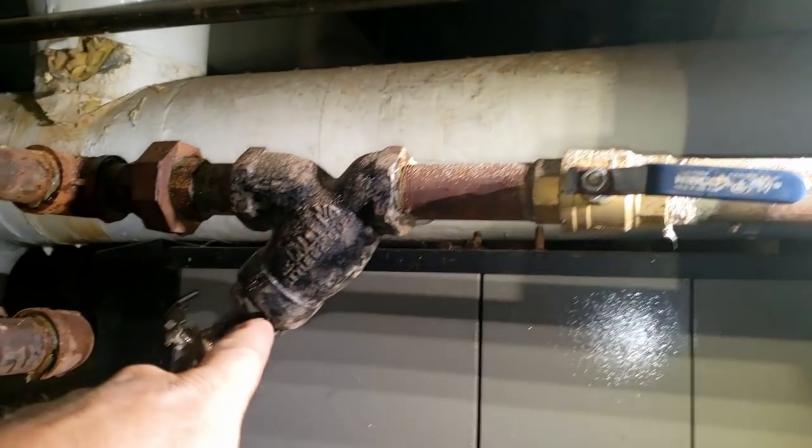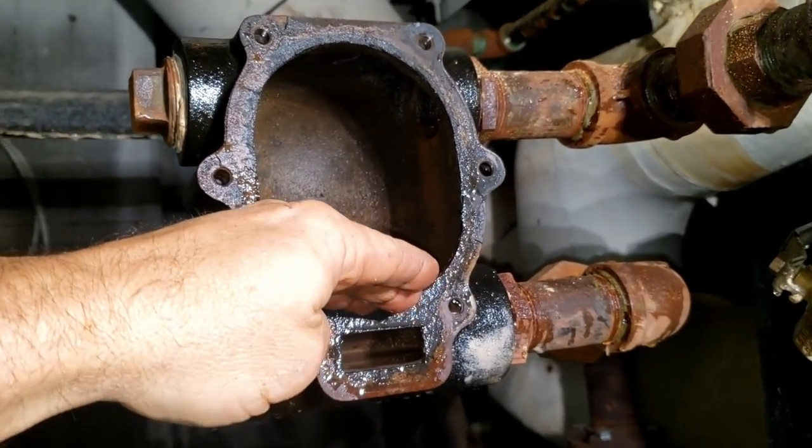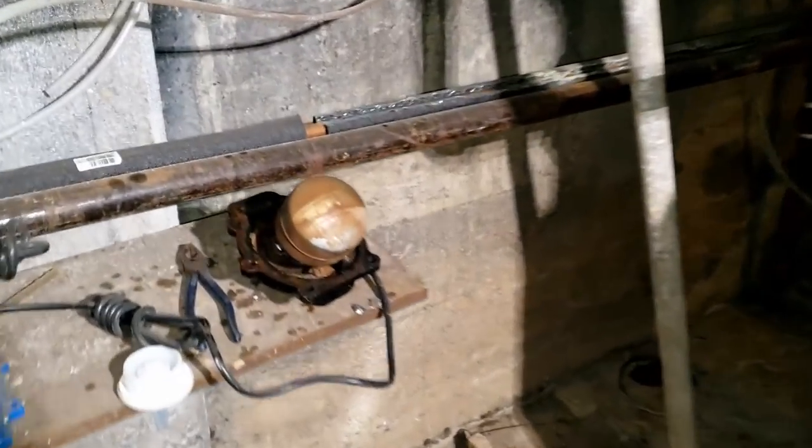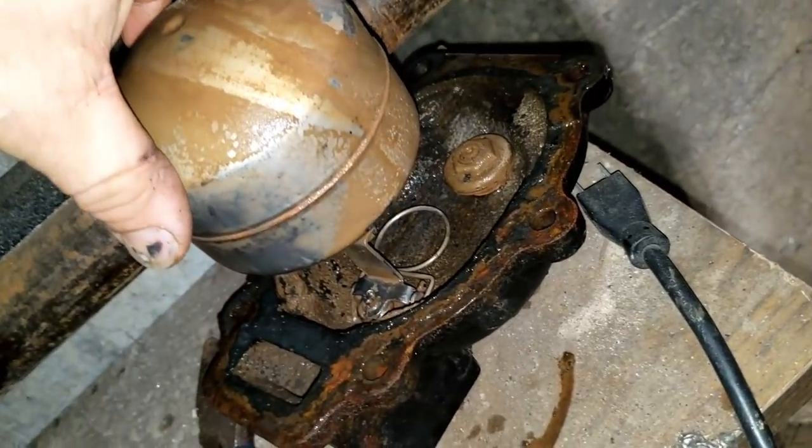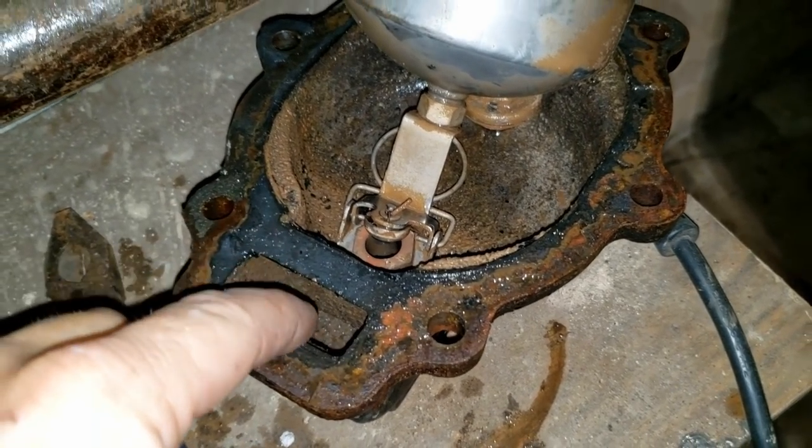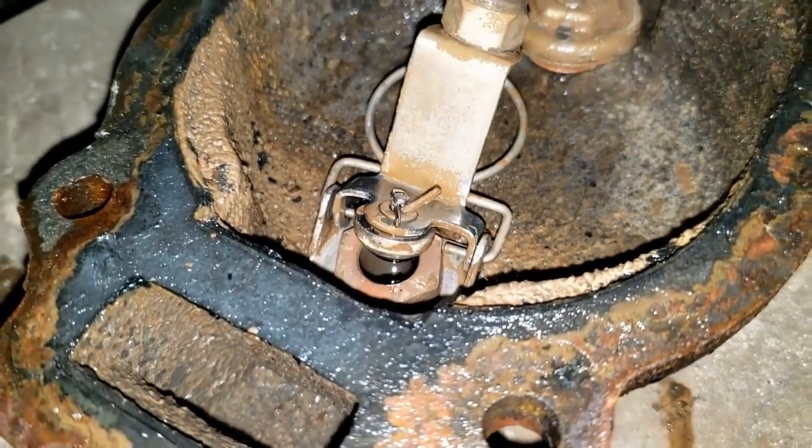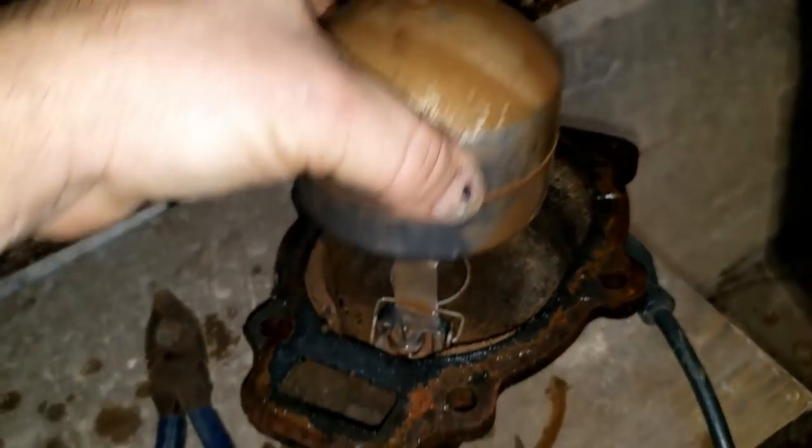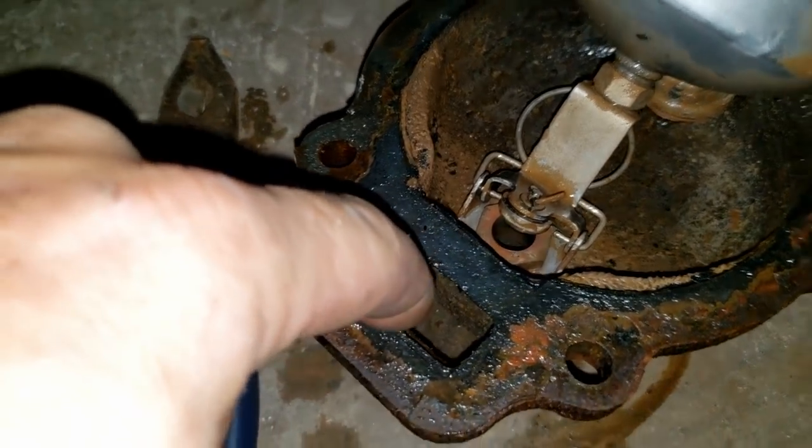This is completely sealed and the water comes in from this top line here on this boiler, goes through, there's got like a blowdown valve so to speak here, comes across, goes into the top. And as it accumulates, it comes up and it rises up and then it will lift this float higher. When the float lifts up higher, it opens up the seal right there and blows the water on through this bottom compartment. So as you can see, that's the seal for it. It's a stainless steel thing. Now there's something inside of this ball - it feels like lead or something like that - but stainless steel ball.